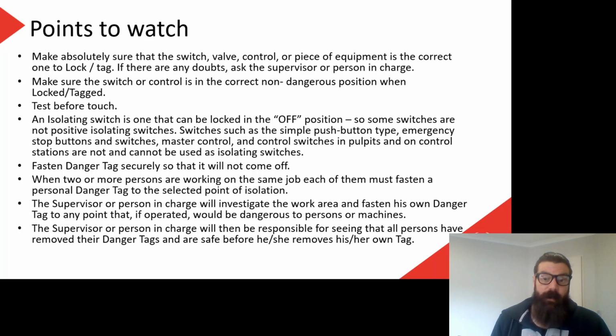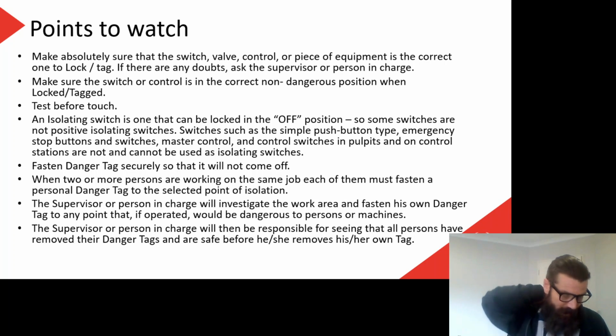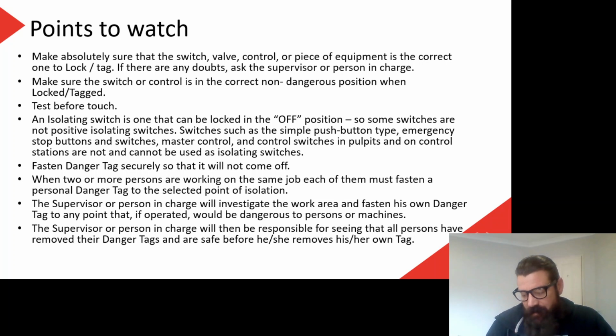An isolating switch is one that can be locked in the off position. So some switches are not positive isolating switches. Switches such as a push button type or an emergency stop or switch, a master control and control switches in pulpits and on control stations are not and cannot be used as isolating switches. Okay, so there's a little bit to unpack there, and this might be something I talk a little bit more about on the conference call, but if we think about an emergency stop system such as we would see in our classrooms, it can switch off the power to all of our sockets, but we wouldn't use that emergency stop as an isolator because someone could turn it back on.